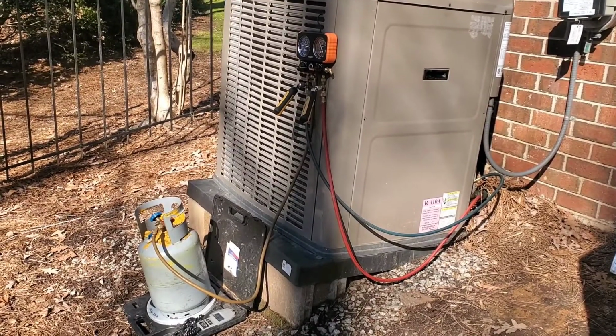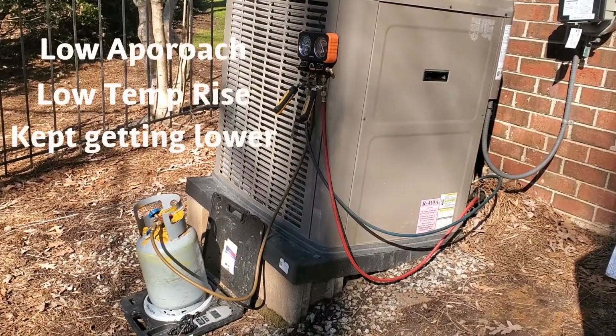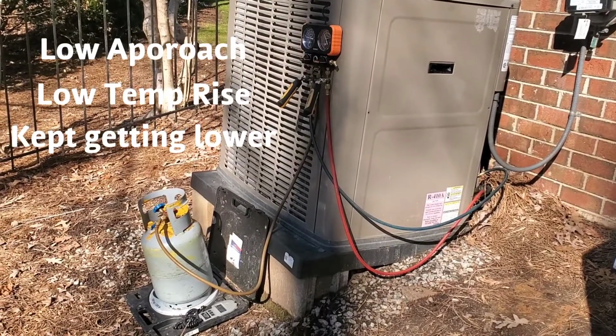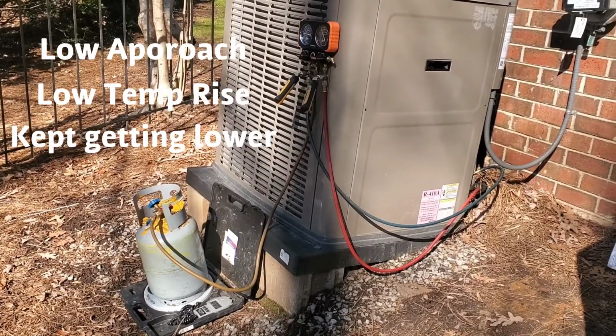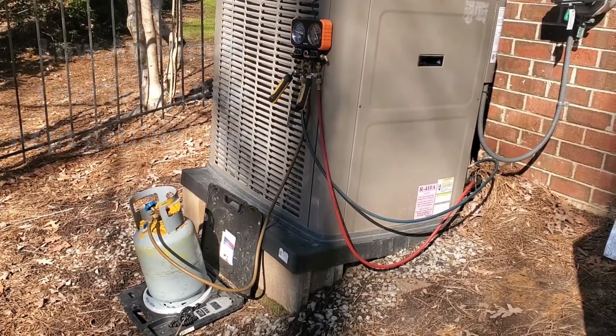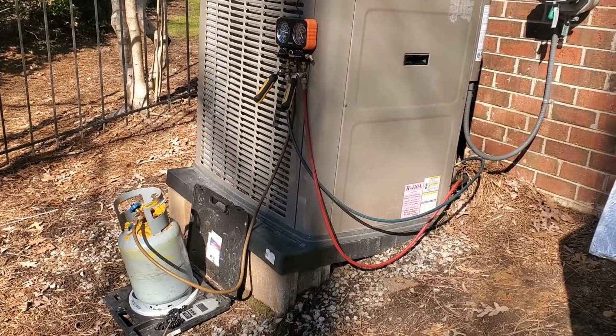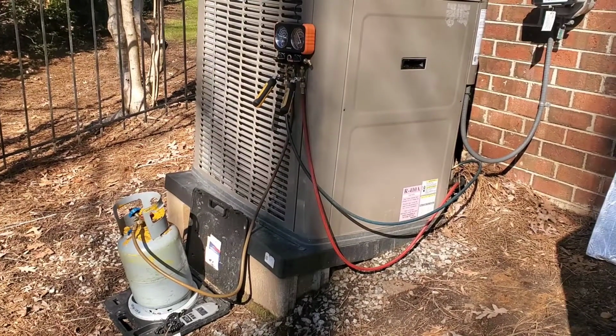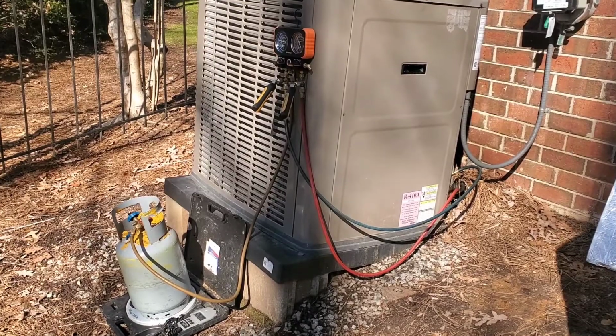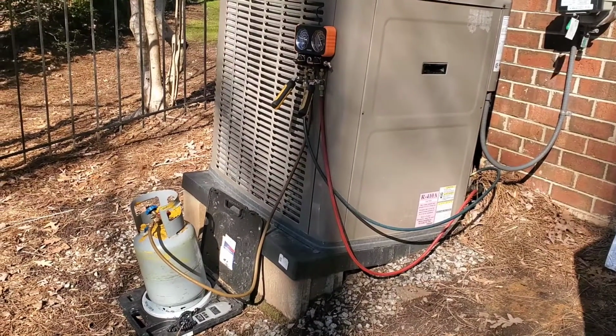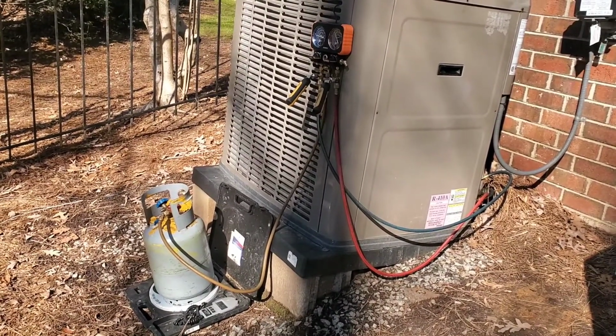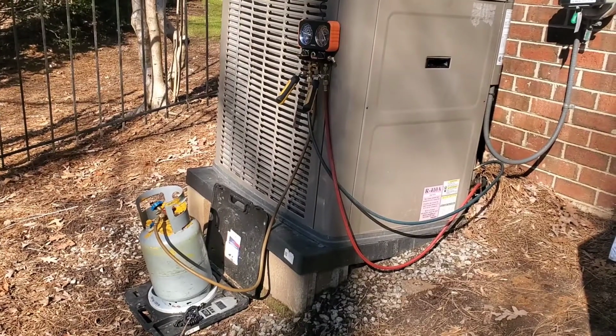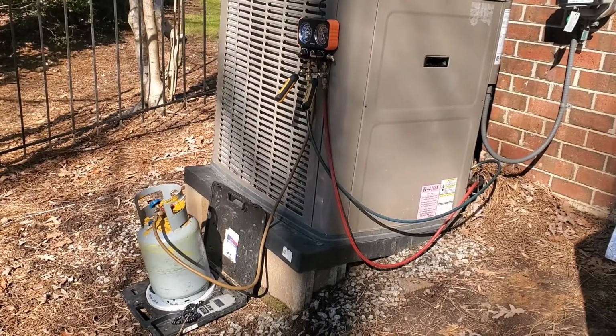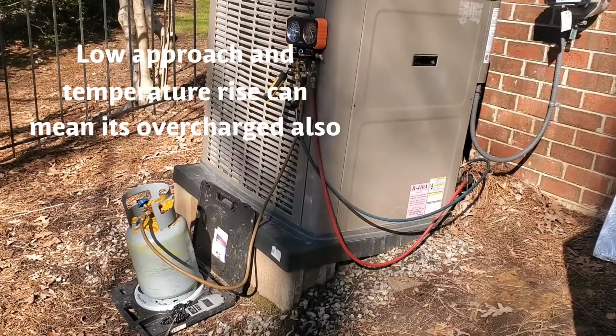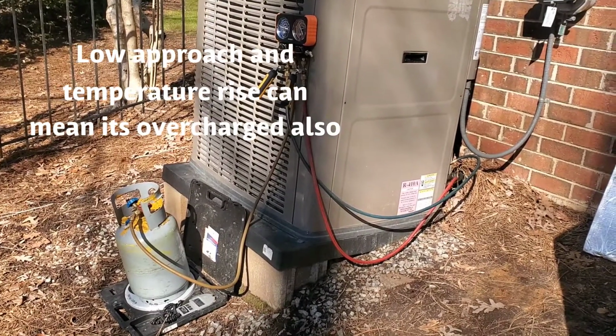Well, as I kept charging it, my numbers started getting worse. My approach went back to zero, and I was just not happy with it. My delta T went down to like 12 degrees, which we know is not good. We want to see something at least 16, 17 degrees even on a cold day. It's 35 degrees out here. And so I decided to take some of that refrigerant out. And what I learned, as you'll see from the next slides, is that when you overcharge a system, your approach can go back down to zero.